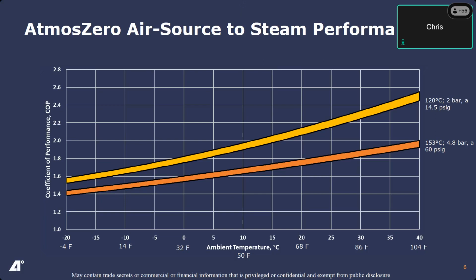If you do tie this to process cooling or waste heat, you can actually still use the same chart. So this is the air temperature or water temperature entering the exchangers. And so in the case of a cooling tower where you have, call it 70°F water coming in, you'd be about 21 Celsius, and your COP on a building would be a little over 2 typically. One thing that we do is we will run case-by-case analysis. So if you guys have an application that you want to take a look at, you can send me an email. I'll send you a questionnaire. You can plug in some information around steam profile, energy pricing, and footprint, and then we will give you a very site-specific technical and economic output to show you kind of how we compare both technically and economically versus electric boilers and gas boilers.